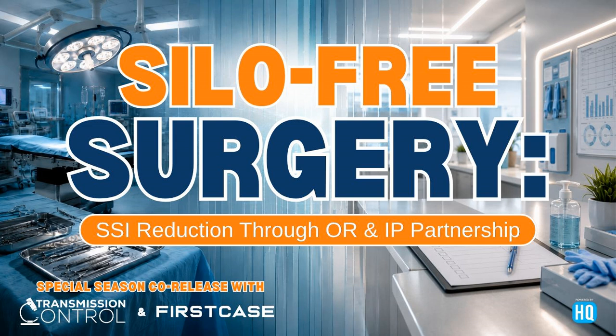So we're mimicking what's happening. Of course, it's not to the extent that the hospital is going through, but some things are simulated in that condition. And I think that is a very important thing that needs to be considered when you're doing validations for reusable medical devices, and where the IFU is part of that. Right, where you have to take in the real clinical environment, where you're backed up on case carts from here to the elevator. What are some of the things that you saw, extra steps or steps not being completed, when you observed the real world conditions?